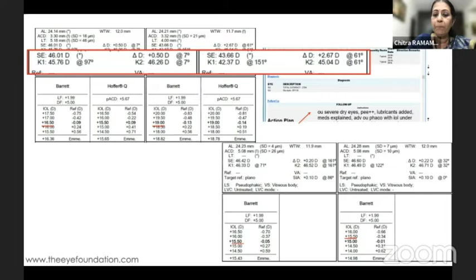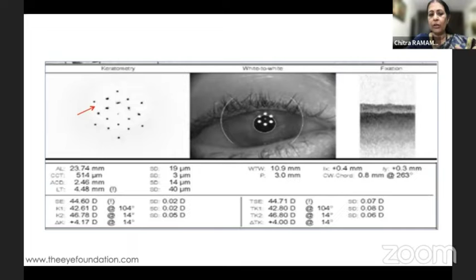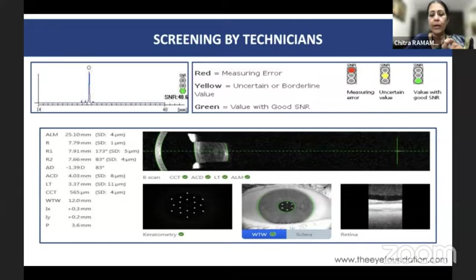Talking about dry eye, even if you look at the LED points on the IOL Master, the fishtail appearance of those spots, or the Placido mires if they are not very regular, these are some indicators. In fact, you should ensure that the same standard technician is consistently doing the measurements for all your patients, or two or three of them as your practice expands. Certain important points need to be looked into. The signal to noise ratio should be more than 2. The standard deviation should be less than 0.2, or a 30 micron difference. These are very critical points which need to be ensured. And you should also look at whether the LED points are distinct and clear. This would allow you to understand whether the measurements have been taken properly.